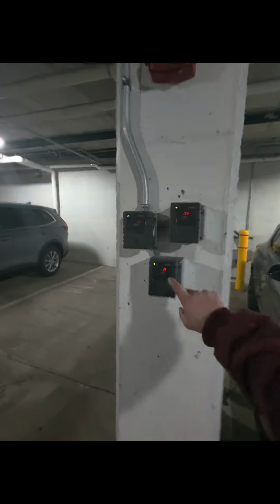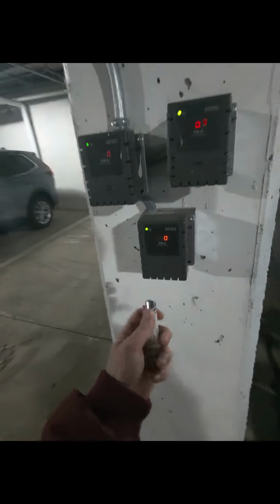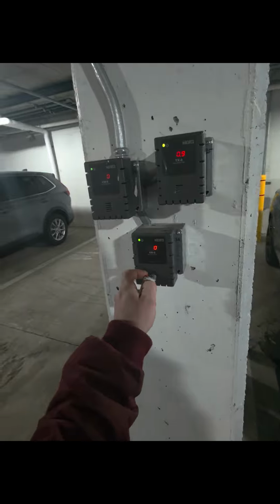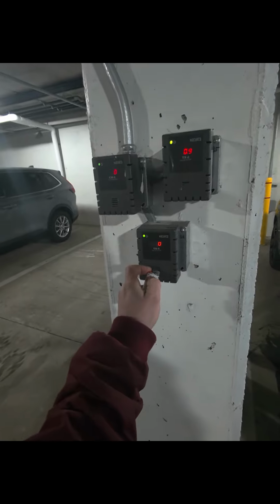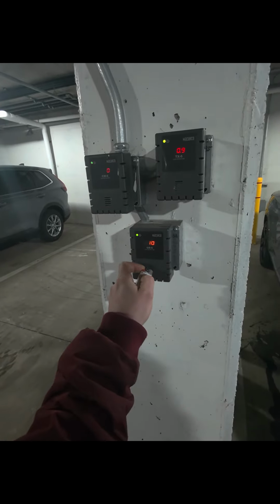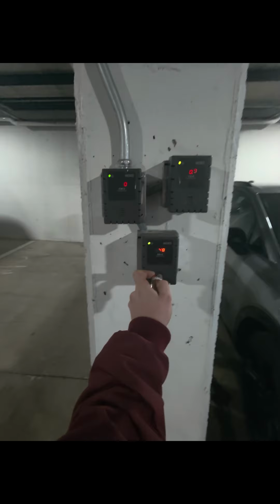So, all right, little bonus clip. I'm going to show you guys how to test the methane detectors. You're going to want to take your butane lighter, hold it like that, bleed some of that gas in there. The sensor's going to go up. You can see that it's in alarm now. Now the dampers are going to open up.